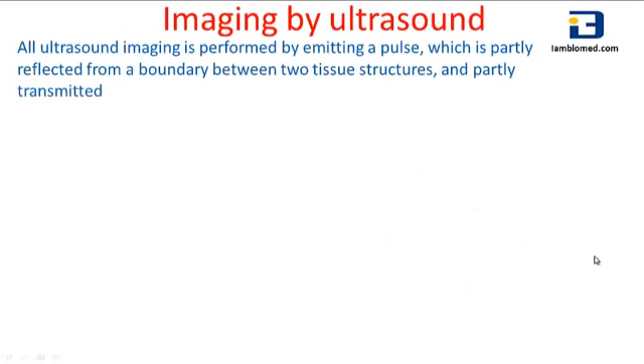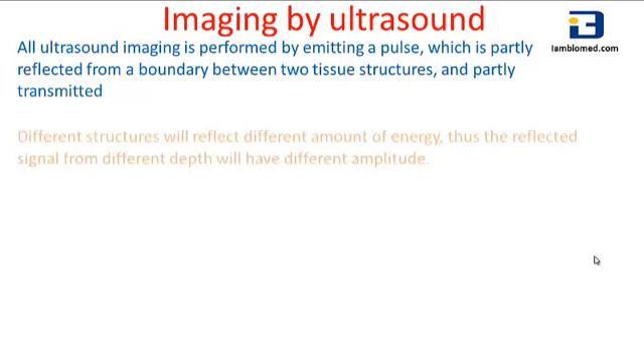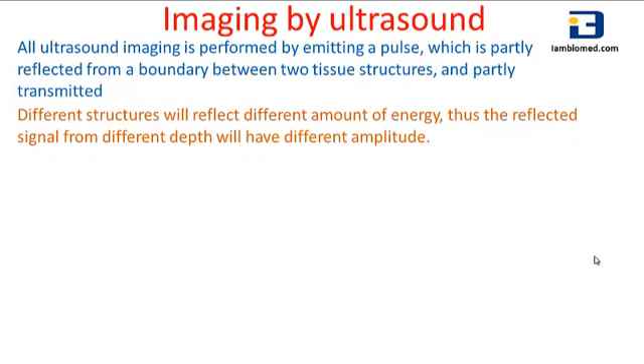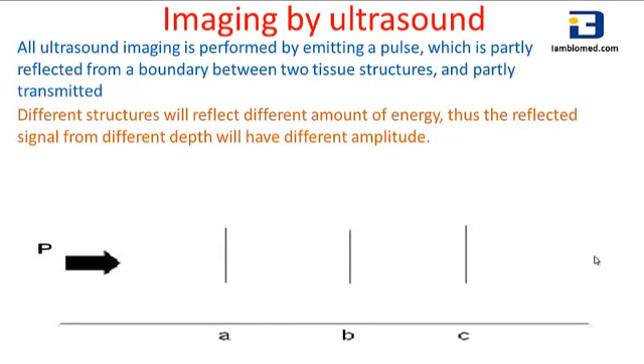Ultrasound imaging is performed by emitting a pulse which is partly reflected from a boundary between two tissues and partly transmitted. Different structures will reflect different amounts of energy, so the reflected signals from different depths will have different amplitudes. Let P be the ultrasonic probe, and A, B, and C be the reflecting structures. These structures do not reflect the ultrasonic pulse directly back to the transmitter — they scatter it, and hence they are called scatterers.